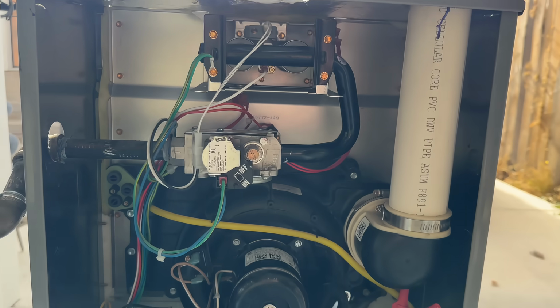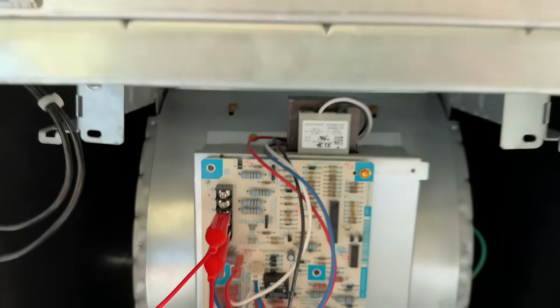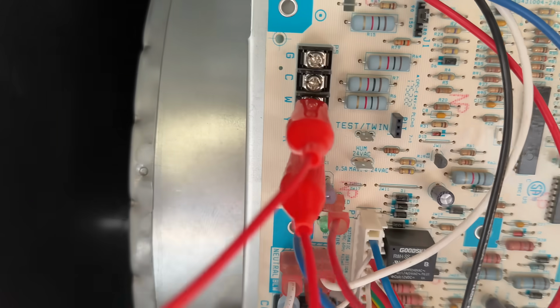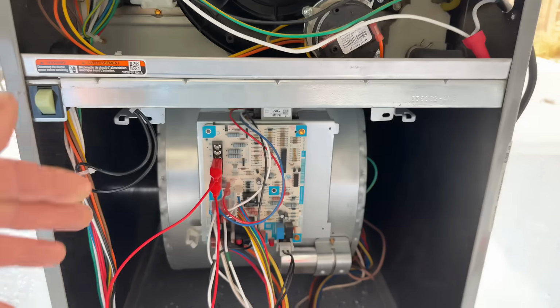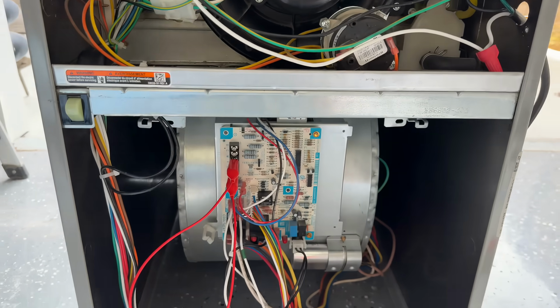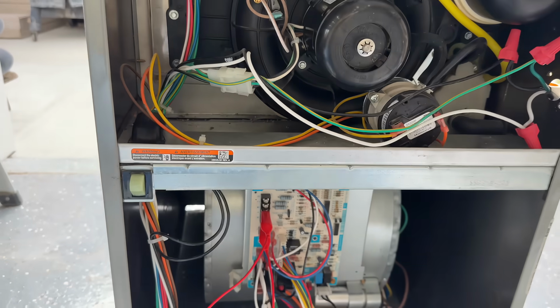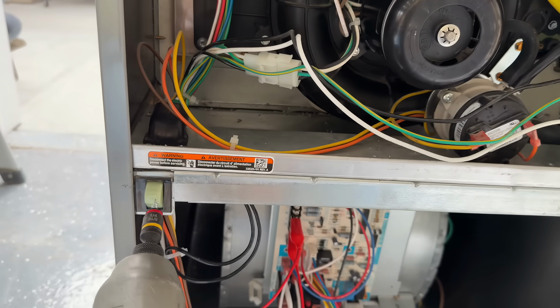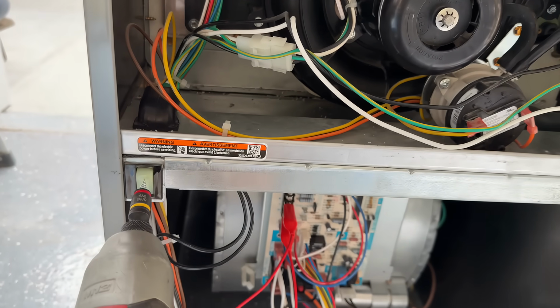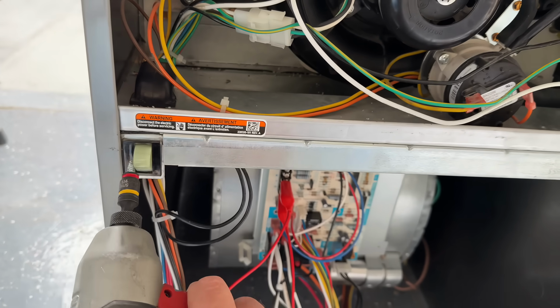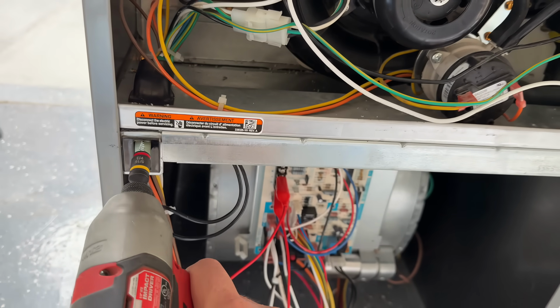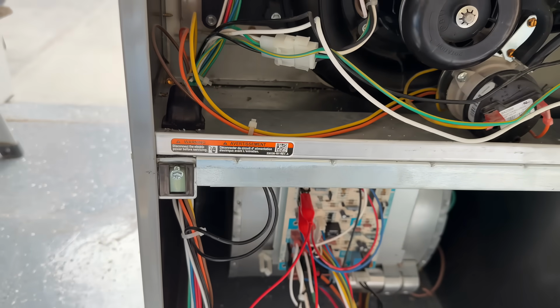So for starters, we're going to bump this into heating mode. We have the R and the W jumped here. That's going to signify as if you went to your thermostat and put it in heating mode. So all we have to do now is jump this switch here. And a little trick is you can take a zip screw and run it in right here, and that will keep this switch closed, just like that.